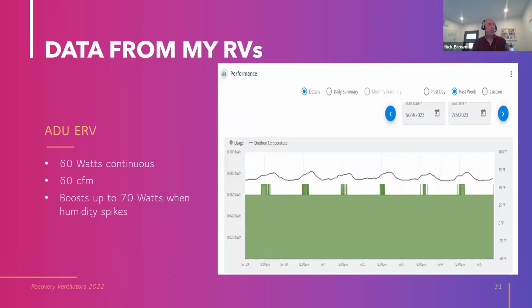Now, I like to share real world data on these to get you thinking about how they work in practice. The ADU one has nothing special fans. They're not ECM fans that are extremely low energy use. They're just standard fans. So it uses 60 watts to move 60 CFM. So 1 watt per CFM. That's not a very efficient recovery ventilator. They make them down in the 0.7 watt per CFM range, even better than that.